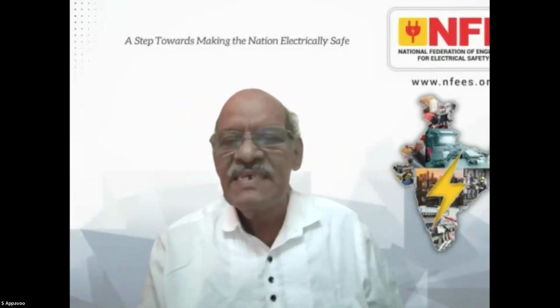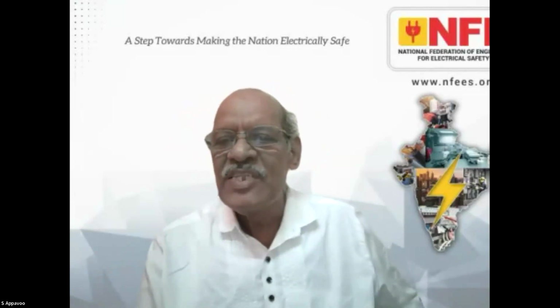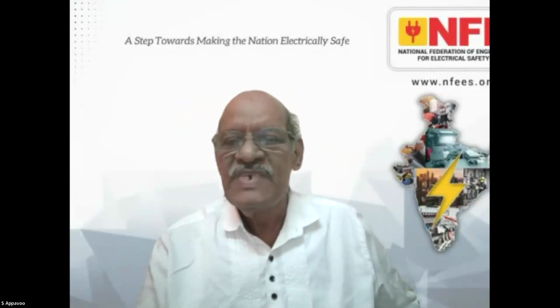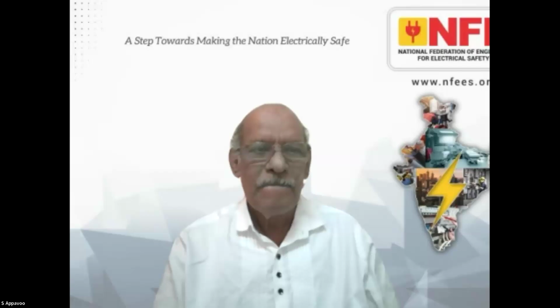Question from Ajit VS: is there a maximum limit for earth pit resistance for a lightning arrestor, and if yes, why? A maximum resistance of 10 ohms is given for Type A earthing, but Type A earthing is not recommended in NBC or in Part 4 of the standard. If you are using a ring or mesh earthing, then there is no minimum or maximum limit at all. You just need to put a proper mesh, that's all that matters.